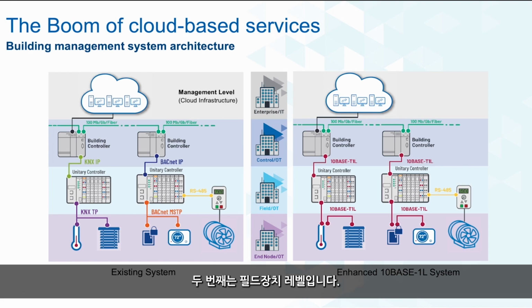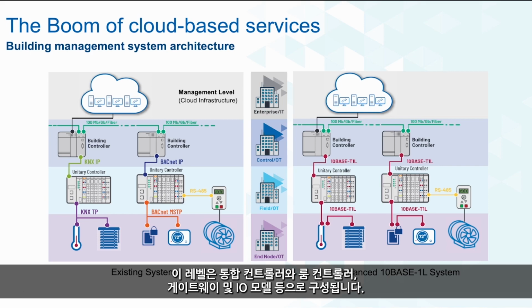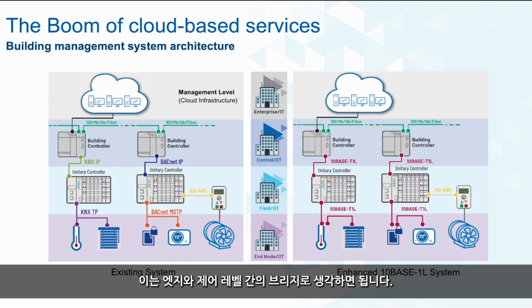Second, we have the field devices level. This level is made up of unitary controllers, room controllers, gateways, and I/O modules. It's considered the bridge between the edge and the control level.